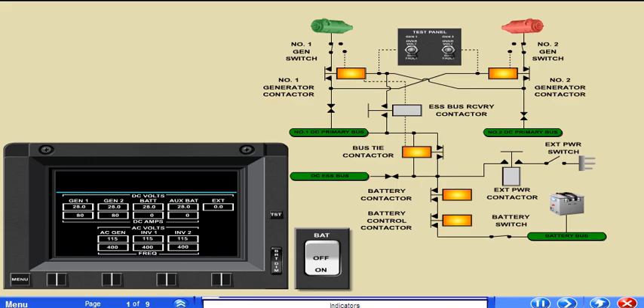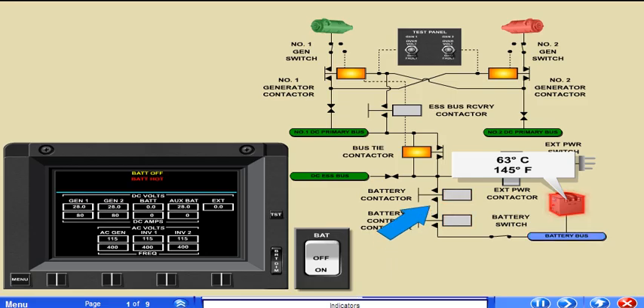The red battery hot message will illuminate when the battery temperature, 63 degrees Celsius, 145 degrees Fahrenheit, or higher, causes the battery to automatically disconnect from the system. The battery off caution light also illuminates. The battery is isolated from all but the battery bus and will not be charged.